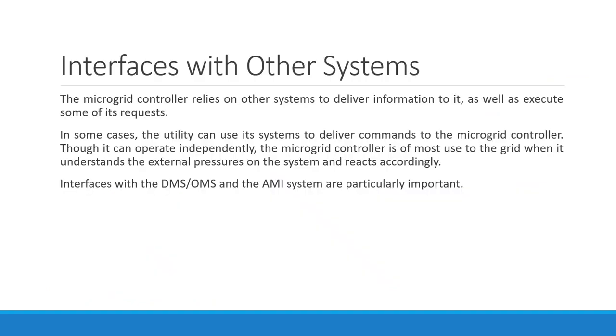Then interface with other systems. That is again part of the microgrid building blocks. The microgrid controller relies on other systems to deliver information to it. We already talked about IEDs, as well as executes some of its requests. The microgrid is connected with other systems. There are a number of systems, so certain information will be transferred to that system, and some information will be transferred from that system to the microgrid. So maybe certain requests will be made, like load curtailment. Or if there is a fault, some request should be there.